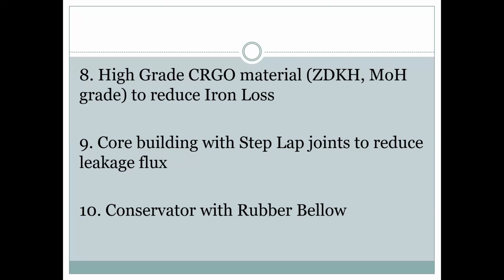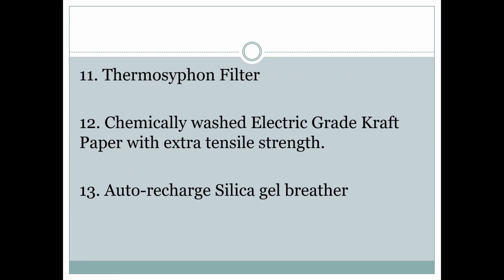So that is now being provided in the conservator, so that no direct air contact is available with the oil. Next, thermosiphon filter. During the cooling operations, there are many insulations in the DC, and they come in contact with the hot oil. So sludge formation takes place, and if this instrument is placed online, the oil will pass through this thermosiphon filter and take the sludge out. After a periodic interval, you can change this thermosiphon filter charge with alumina, and you can use the oil for longer.